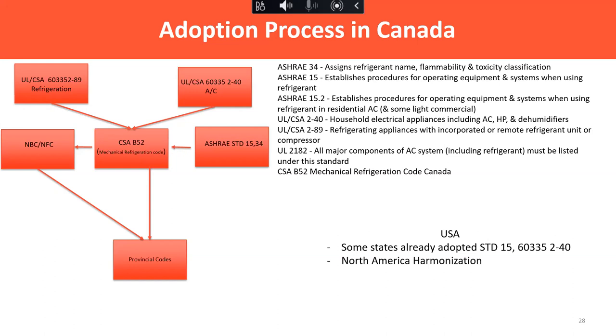B52, A2Ls are in there, but only in a very limited way. And even in the UL or CSA standards, hydrocarbons can be used, A2Ls can be used in very limited charge sizes, typically about 150 grams. Within B52, there may be some other areas where A2Ls could be applied, but these standards like B52, and also the NBC National Building Code and the National Fire Code, are also being updated and revised to include this new class of refrigerants called A2Ls.